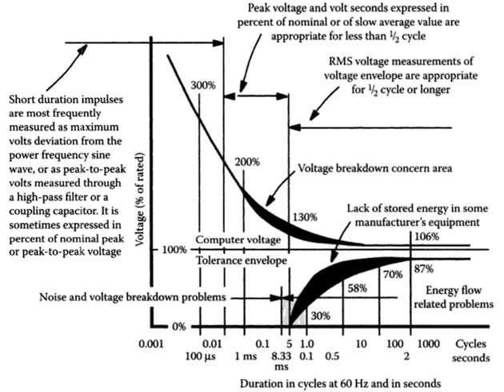In order to sufficiently monitor unforeseen events, Ribeiro et al. explain that it is not enough to display these parameters, but to also capture voltage waveform data at all times. This is impracticable due to the large amount of data involved, causing what is known as the bottleneck effect. For instance, at a sampling rate of 32 samples per cycle, 1,920 samples are collected per second. For three-phase meters that measure both voltage and current waveforms, the data is 6 to 8 times as much.